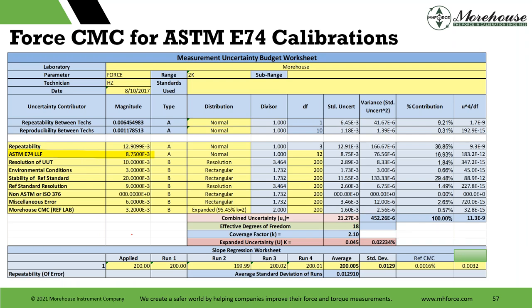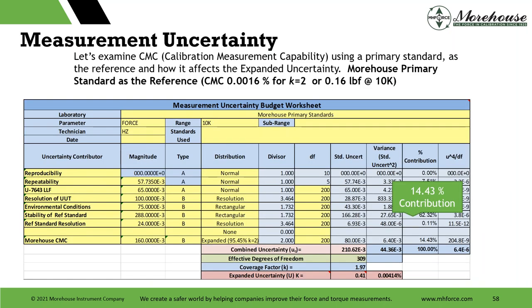Basically, this one you can see was done at the 200 pound test point, and at the 200 pound test point, on a 2K range, you achieved 0.02%. And if we look at different contributors, here's just looking at that right here overall. The reference standard to perform the calibration.